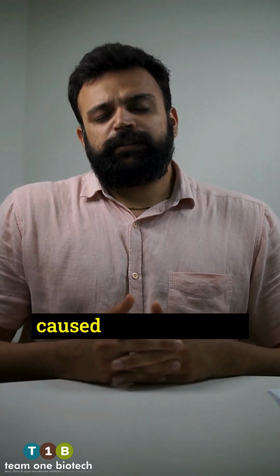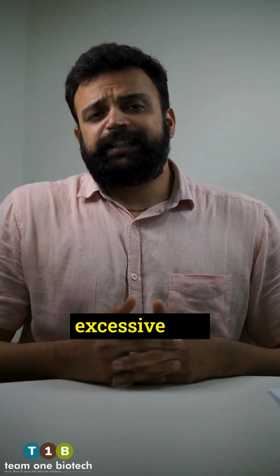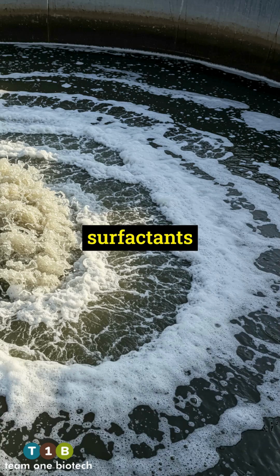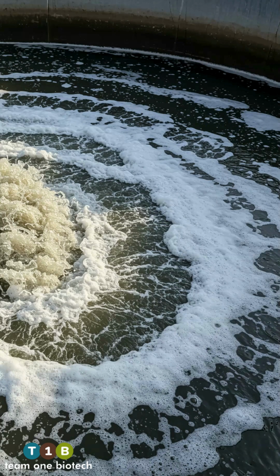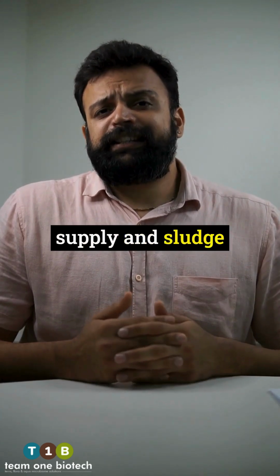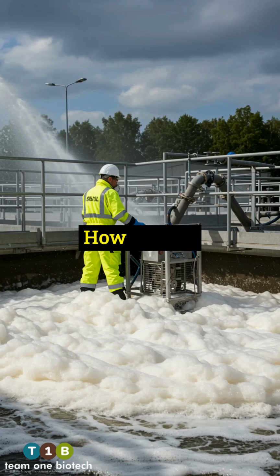Third is foam or scum. Foaming is primarily caused by filamentous bacteria, excessive fats, oils, and surfactants such as soaps and detergents, protein-rich wastewater, unbalanced nutrient supply, and sludge with poor settling qualities. How to fix it?